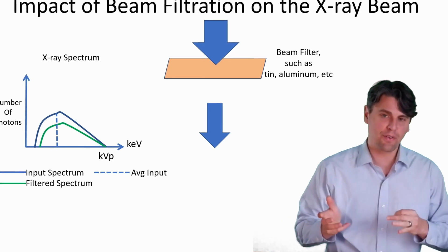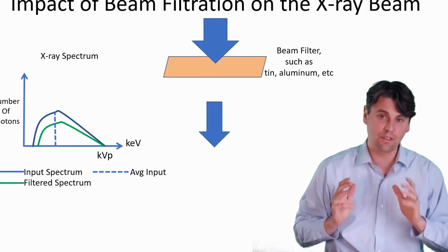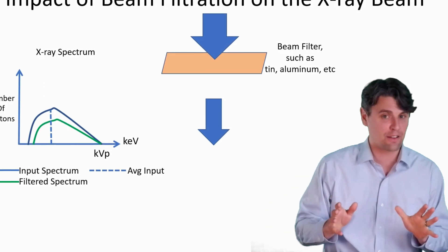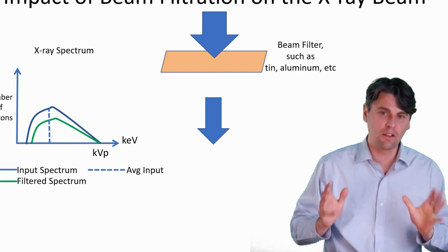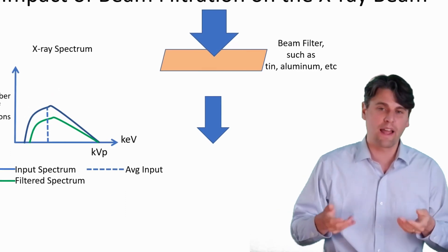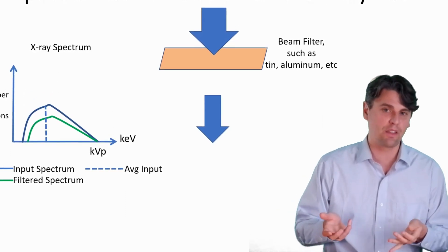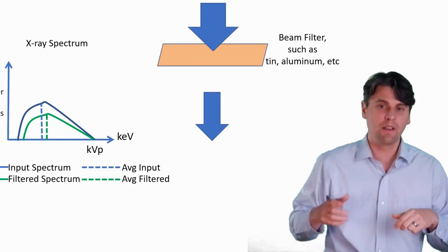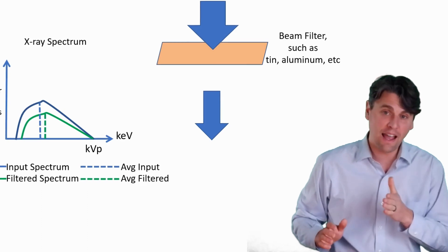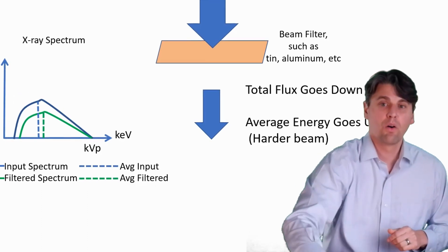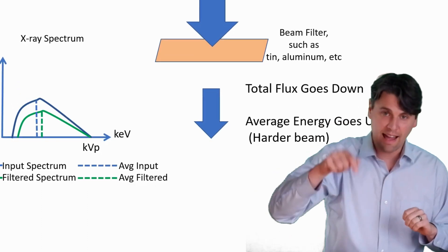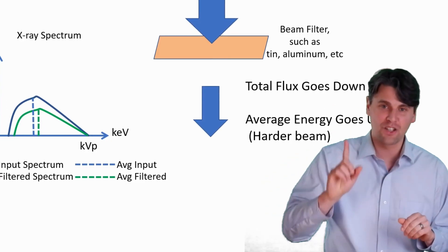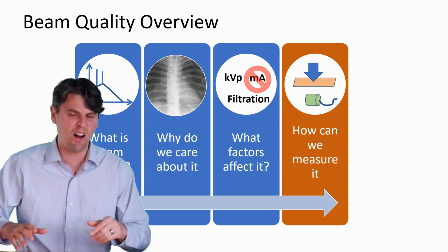So the output spectra for the x-rays after they pass through that thin sheet of metal is actually going to be less x-rays, right? So we call that lower flux or a lower exposure is going to be making it through. But if we look at the average energy of that beam, it's actually going to be higher now. So we have less x-rays, so lower flux, but higher average energy. Now you know the factors that affect beam quality as well.